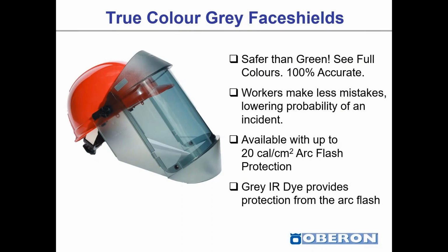And then specifically regarding face shields and the lens technologies for arc flash PPE, there are now gray face shields in the market. Compared to green, they are safer. And what I mean by safer is they allow workers to see their work clearly. They allow for 100% color acuity, so your colors are 100% accurate versus being altered or even shaded out based on the yellow or green lenses. When workers see their work task clearly, they make fewer mistakes. They lower the probability of an incident. And this type of technology currently is available as a standalone face shield up to 20 calories.